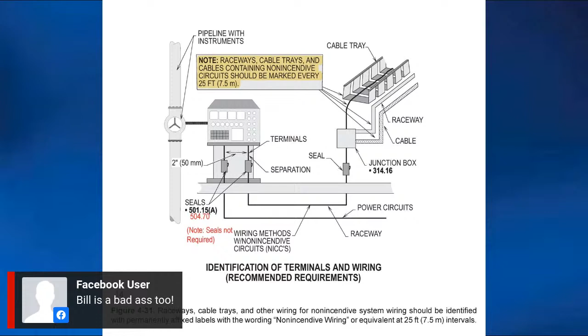Notice then, fellas, it's light yellow, and we would want to make everything light yellow where we terminate. But I've seen them use solid yellow cables for non-incendive, and then just take a cable and spray it light blue. In their PM manual, light yellow and light blue were non-incendive and intrinsically safe. You're not to work on them, not to touch them unless you're qualified to do so and have a reason to.